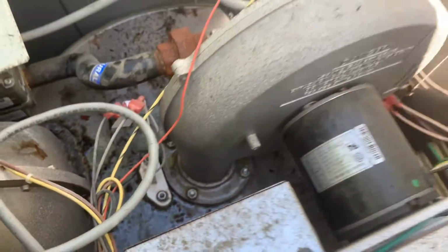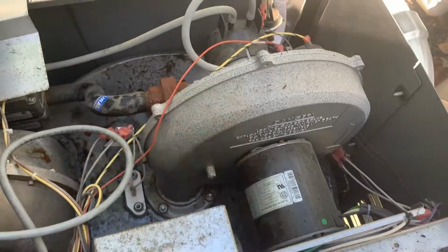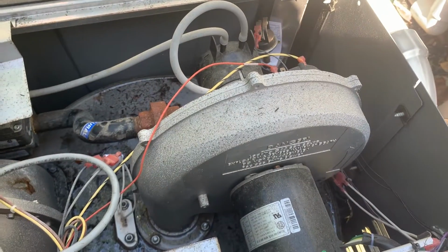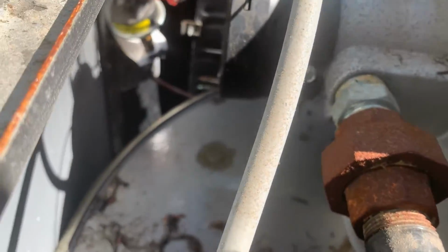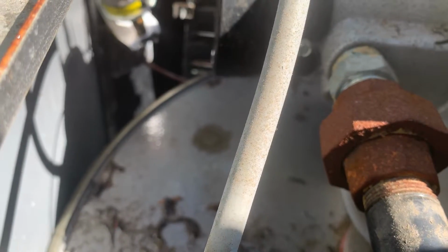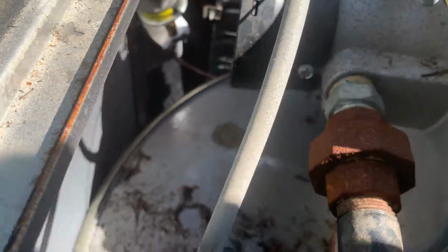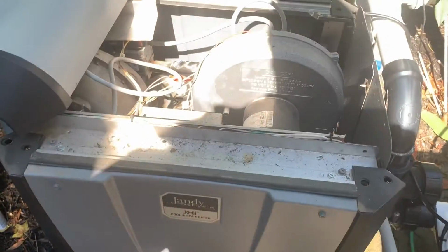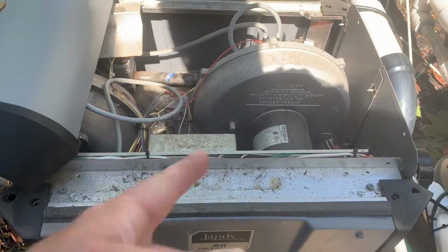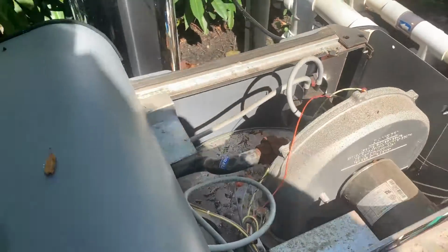I'm going to show you. Excuse me, I'm doing this one-handed. This is the gas valve and draft fan. As you can see, there is water dripping from that. So the heat exchanger has failed, and it's leaking into the draft fan.